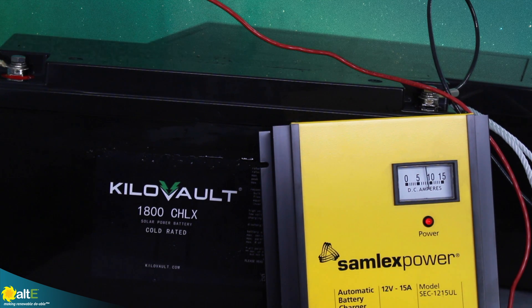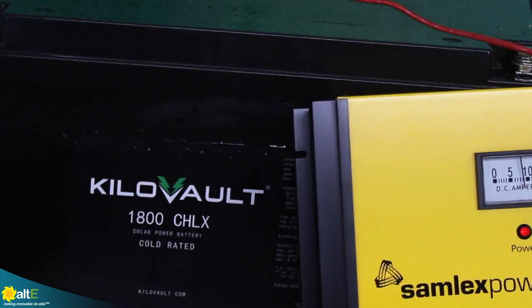So even after it allows the battery to start charging again, the heater is actually going to stay on until the battery reaches 50 degrees. So again, it just really gives it a little extra heat so that it's not going to just immediately start dropping down and turn off again. So you're not bouncing back and forth.